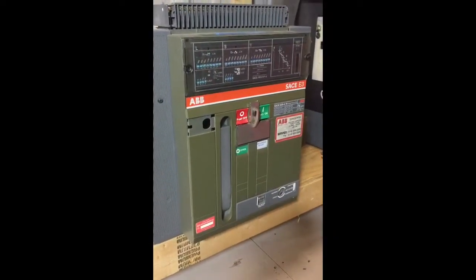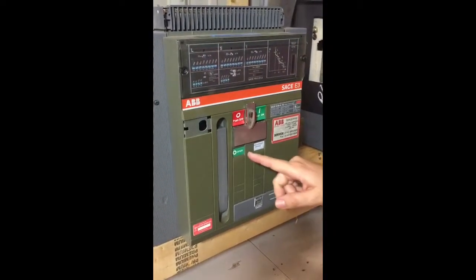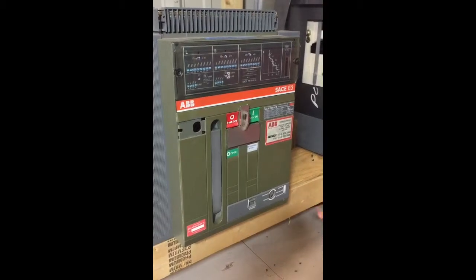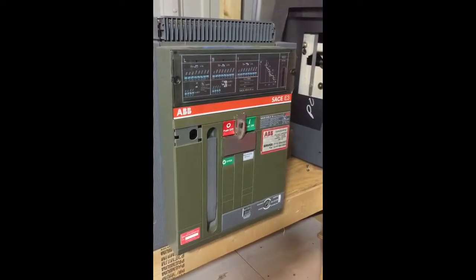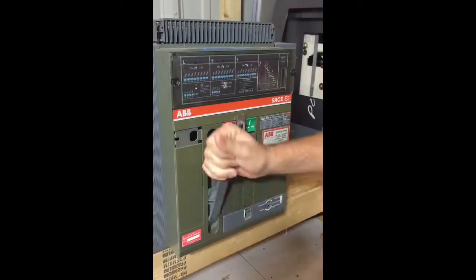So here we have an ABB E3 breaker and it is currently in the open position. We're going to close it remotely using the Chicken Switch SACE-1 actuator. But first I need to charge the spring, so I'll use a charging handle.